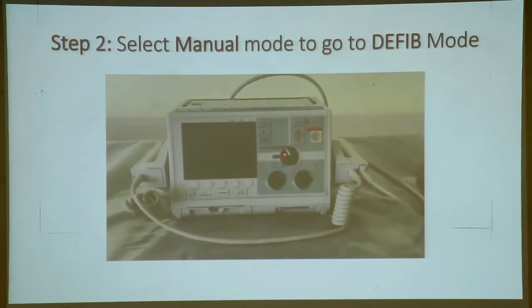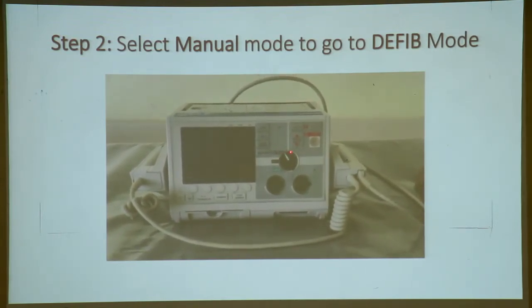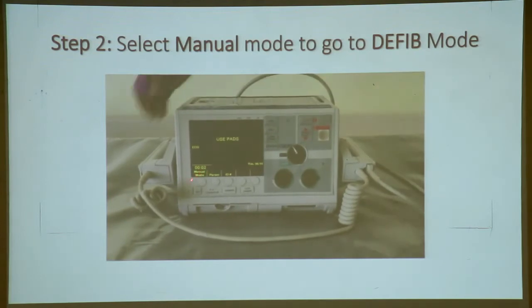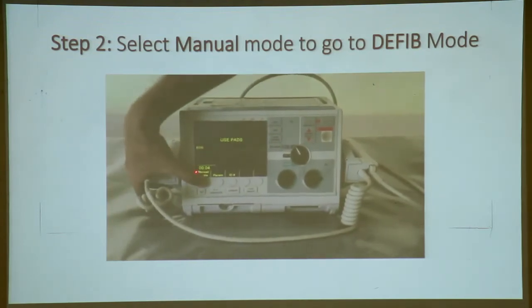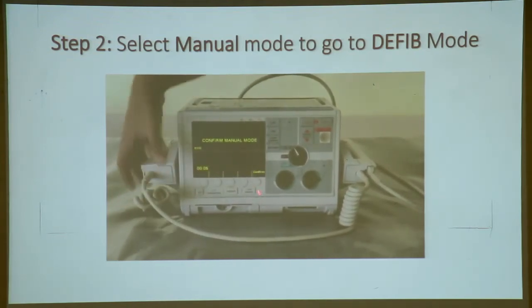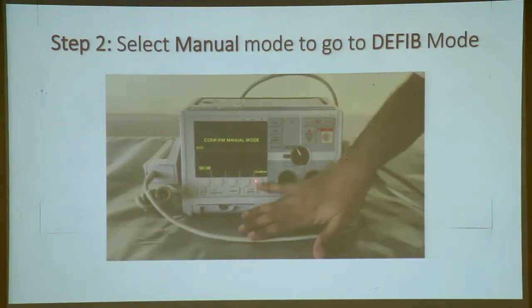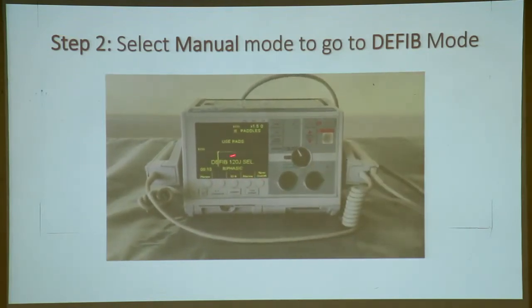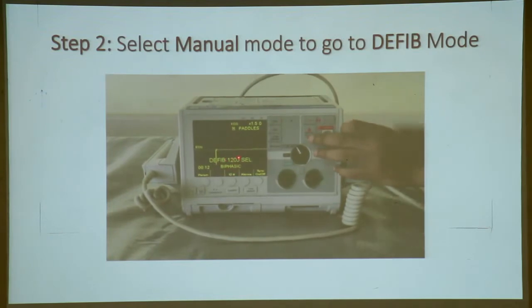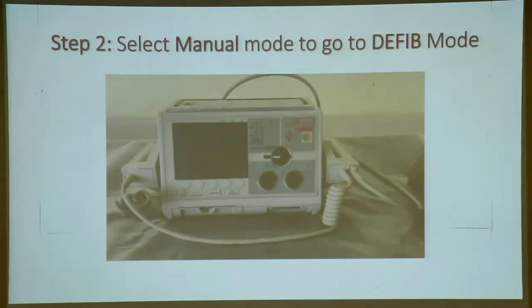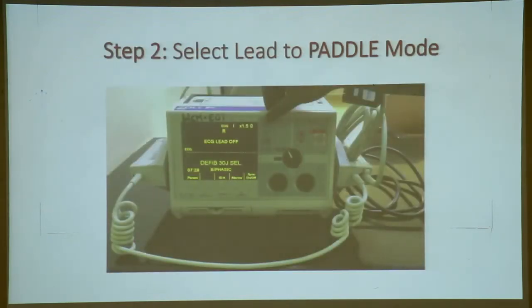I'm just switching it on. The defibrillator is switched on. Right? I press this AED mode button here which says manual. It asks me to confirm whether I want to go to manual mode. I confirm. Now it has come to defibrillator mode. 120 joules. Right? So once you are in defibrillator mode, you select 30 joules. The defibrillator paddles are kept apart where they are. Then you select the lead.